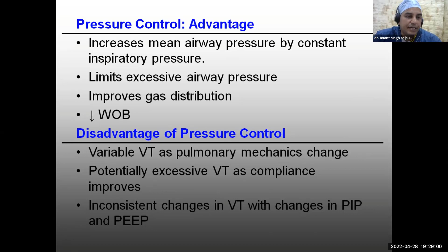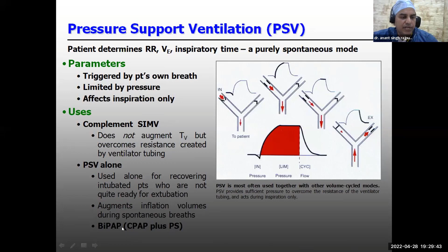Coming to the next mode, that is pressure support mode. It is just like pressure control mode. The squarish pattern is followed, but here the trigger is by the patient. It is not time triggered. It is triggered by the patient. So a spontaneously breathing patient will be on pressure support mode. His inspiration will be supported by the pressure support. The other thing that can happen here is you can combine pressure support with SIMV mode, as discussed, for more safety of the patient, right? We'll come to BiPAP and CPAP a little later in coming slides.